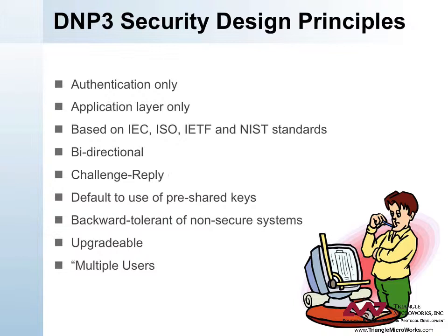Bidirectional: either the master or the outstation can authenticate messages. Challenge-Reply: it is based on the common security concept of challenge and response. The device performing the authentication challenges the sender by providing data that must be included in the authentication calculation. This makes spoofing much more difficult. It also means the receiving device determines which messages must be authenticated. Pre-Shared Keys: DNP3 Secure Authentication Version 2 assumes the sender and receiver have previously shared a cryptographic key through some method other than DNP3. DNP3 Secure Authentication Version 5 provides a method to permit these pre-shared keys to be changed remotely and securely. Backwards Tolerance: the specification attempts to make it possible for a non-secure device to identify that a secure device is using a portion of the protocol it does not recognize, without an authentication message causing the non-secure device to fail.